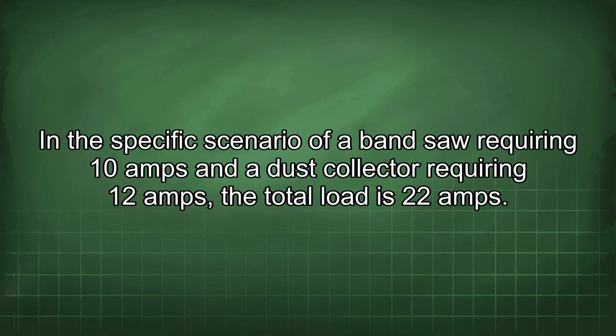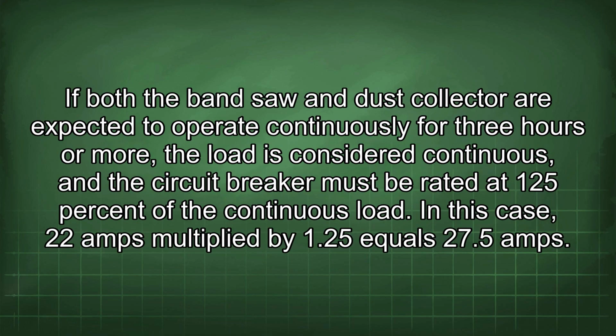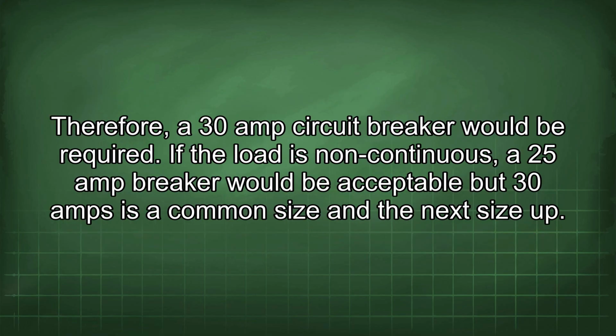In the specific scenario of a bandsaw requiring 10 amps and a dust collector requiring 12 amps, the total load is 22 amps. If both the bandsaw and dust collector are expected to operate continuously for 3 hours or more, the load is considered continuous, and the circuit breaker must be rated at 125% of the continuous load. In this case, 22 amps multiplied by 1.25 equals 27.5 amps. Therefore, a 30 amp circuit breaker would be required. If the load is non-continuous, a 25 amp breaker would be acceptable, but 30 amps is a common size and the next size up.